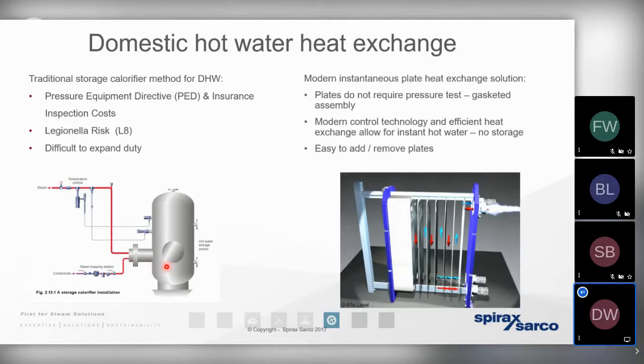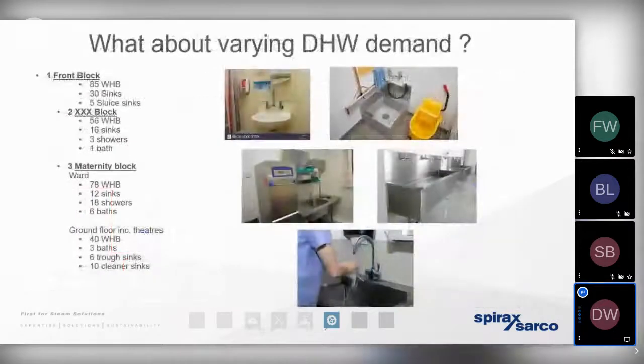So let's look at a typical application, and the application I've chosen here is the generation of hot water for a hospital. Now, it could easily apply to any other building or process that's using hot water. A hospital just happens to be the application that I've chosen here. So whenever we've got a requirement for hot water, we typically refer to that as a draw-off point. And all of these draw-off points can serve a different purpose, and they can all have a different fluctuating demand around site at different parts of the day.